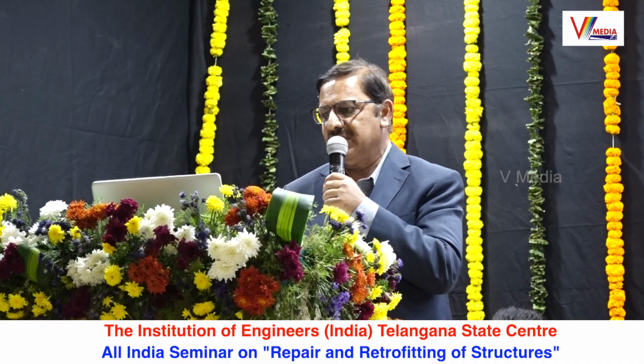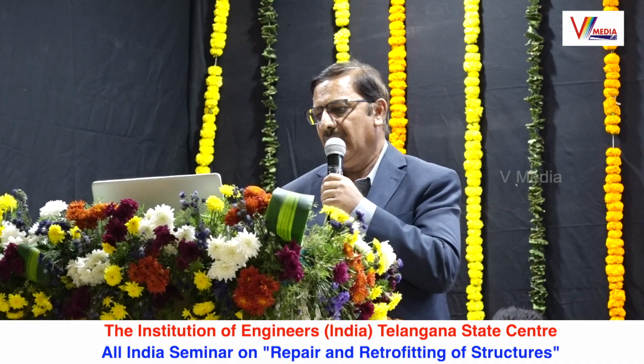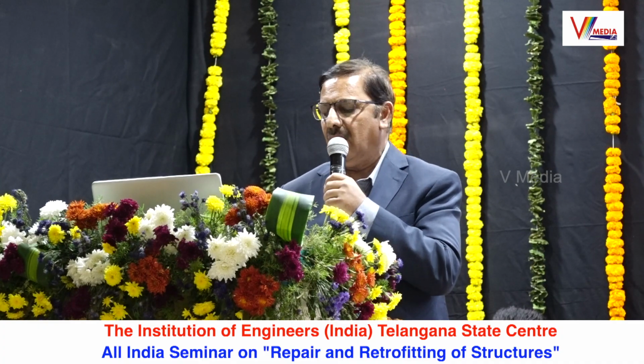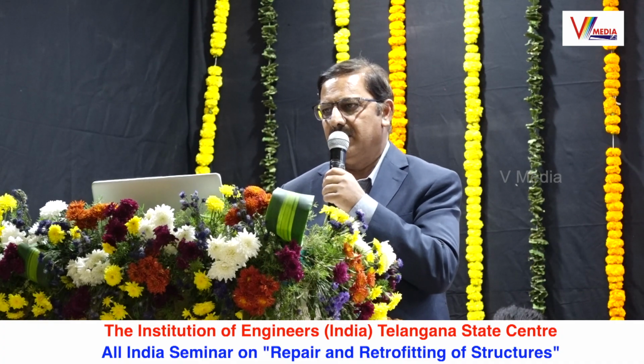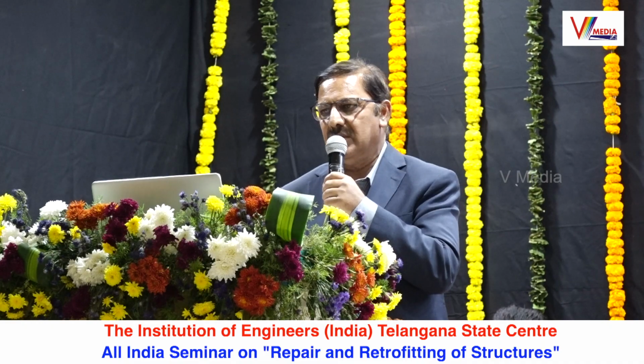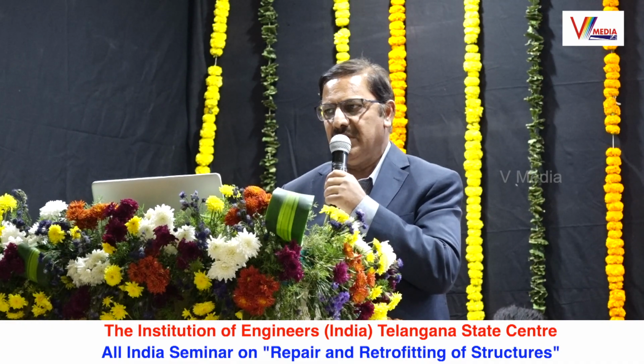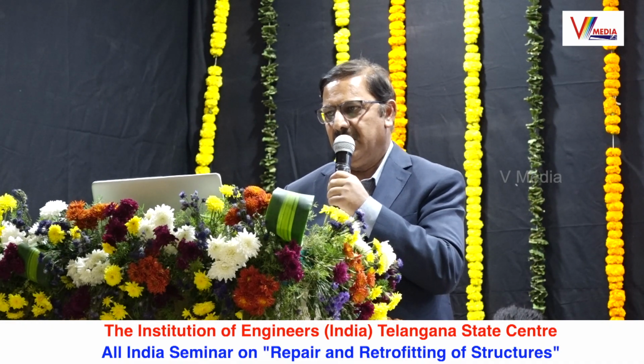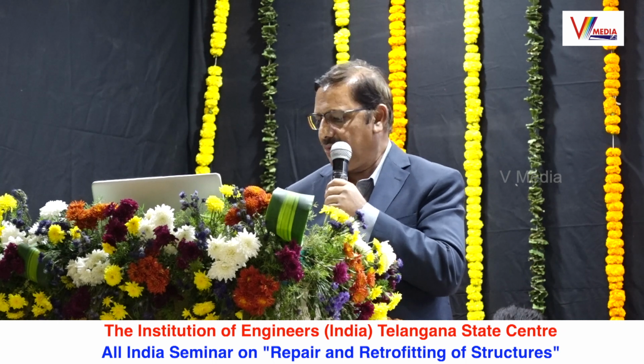You are seeing on the top that anodes and cathodes are formed. As you apply cathodic protection, you go down, and you will see all the sides have become cathode. You are making all the anodes cathodes. Once you reach a negative potential of 850 millivolts, for steel in soil, you get cathodic protection.